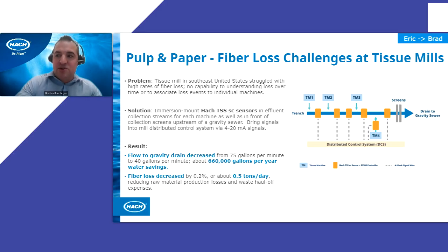The continuous measurement allowed excursion traceability to specific tissue machines and events such as spills, production changeovers, maintenance activities, and shift changes. The previous challenge of foam presence and sample line clogs resulted in inaccurate readings. That was avoided due to the TSS sensor's differentiated design features, which enabled reliable measurements even in harsh environments.